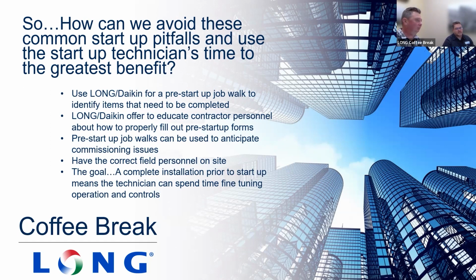Absolutely. So having the right job site conditions matters. You want to start the unit and commission it in its final operating state, or as close to the final operating state as possible, so that you have efficiency of turnover and you don't have as many problems after the fact. Yep. Because the other thing we want to avoid is the end user, the owner, having a bunch of warranty concerns and losing faith or trust in the equipment because it fails prematurely. Exactly. And a lot of that is from starting it in a bad condition. Yeah, that could be avoided.